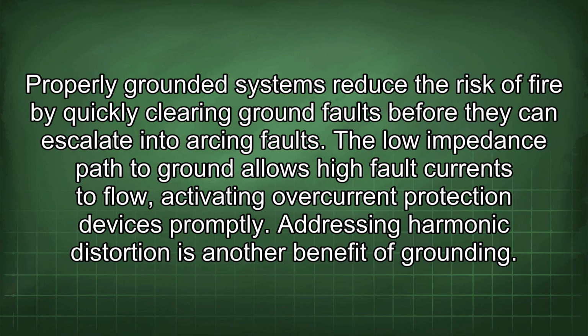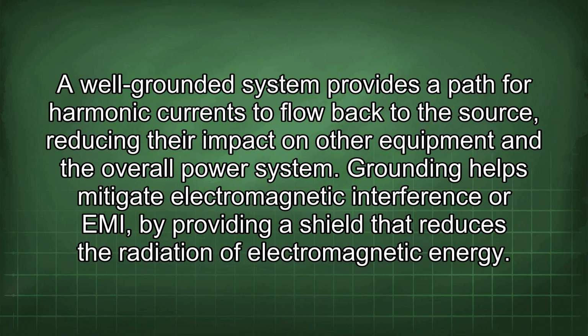The low impedance path to ground allows high fault currents to flow, activating overcurrent protection devices promptly. Addressing harmonic distortion is another benefit of grounding. A well-grounded system provides a path for harmonic currents to flow back to the source, reducing their impact on other equipment and the overall power system.